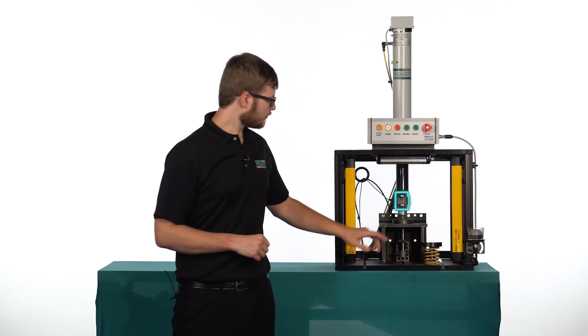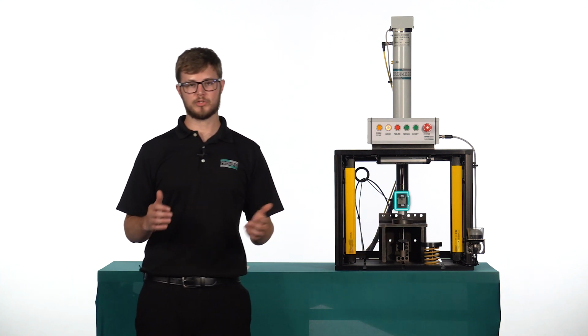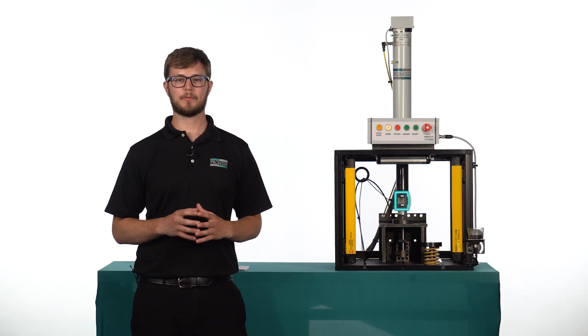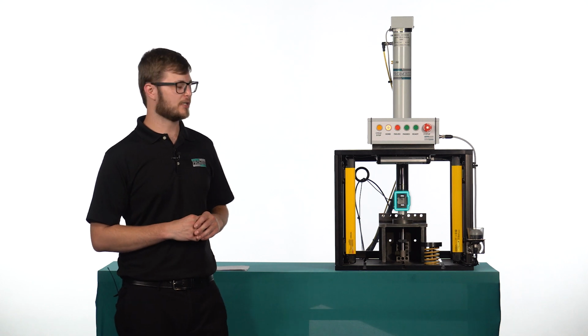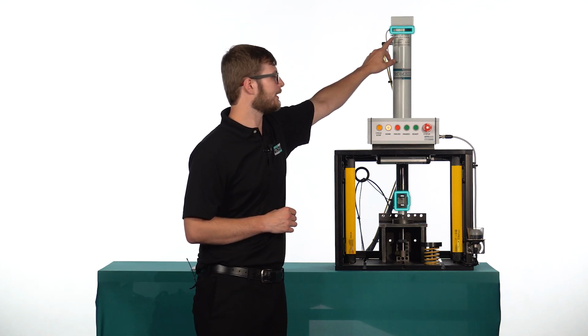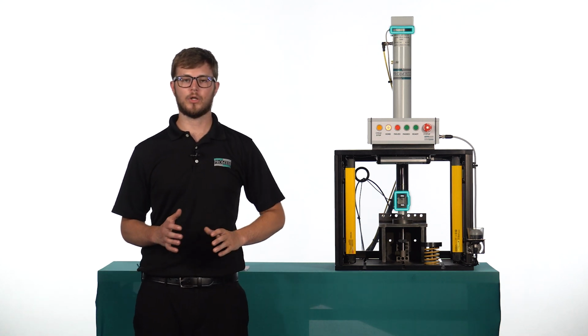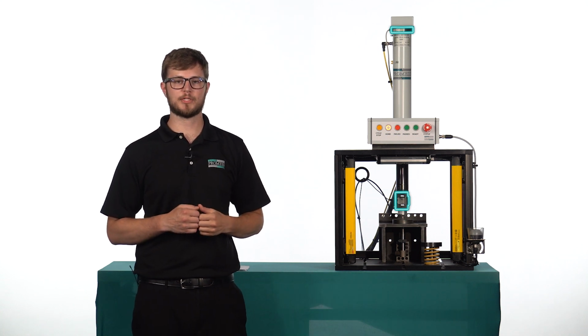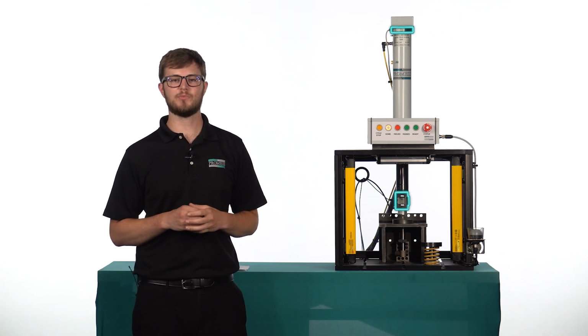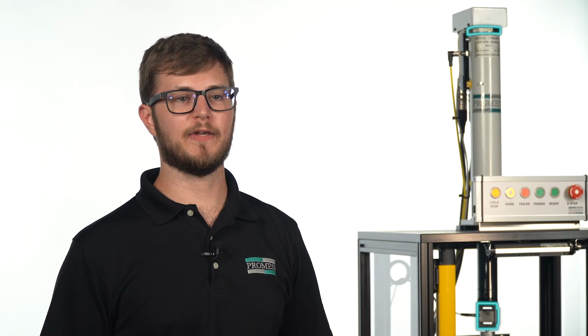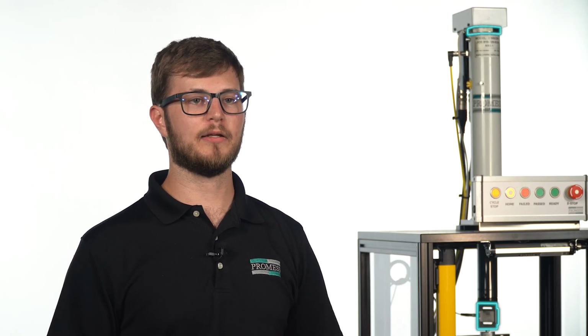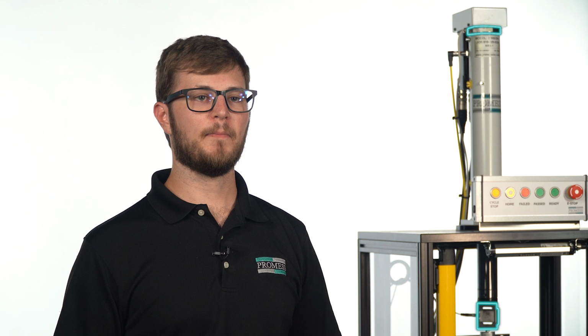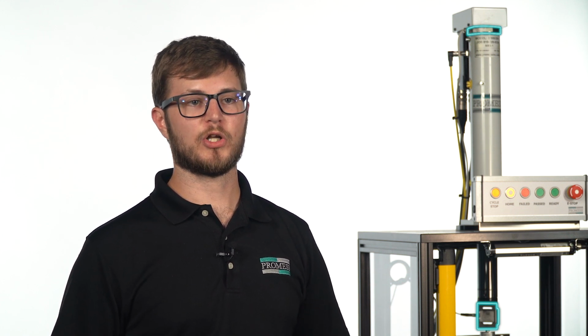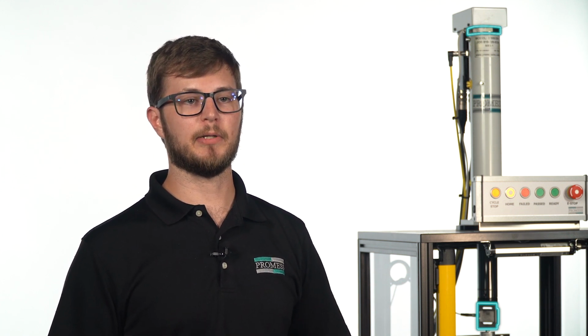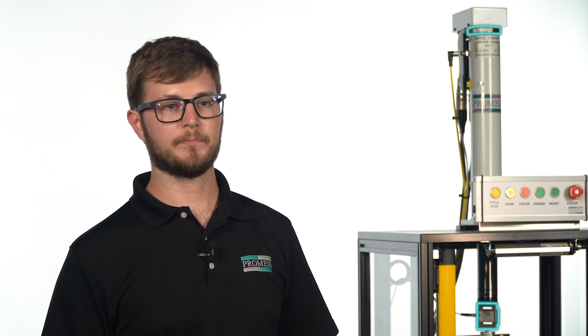We'll start with our overload protected external load cells. Every EMAP comes standard with an internal load cell, identified by the silver band at the top of the press. The load cell takes in and reads force measurements in real time. This gives the machine the ability to feel how much force is being applied to a particular assembly, part, or function, resulting in extreme precision and repeatability throughout your production run.